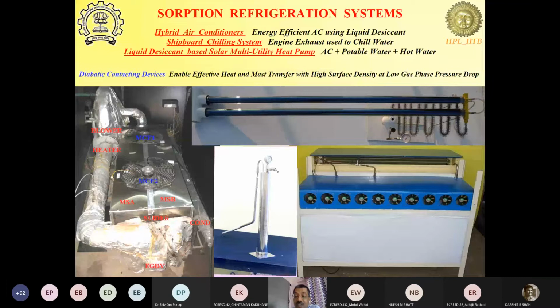And so the evaporator of conventional air conditioning systems, the conventional DX system, is typically operating at 7.2 degrees centigrade. While in the case of chillers, the chilled evaporator might operate anywhere between 3 to 5 degrees centigrade, depending upon the chilled water temperature and so on and so forth. But in this case, by using liquid desiccants to do the dehumidification, you will see that we can increase the evaporator temperature to 12 degrees, 15 degrees, 18 degrees, or even up to 20 degrees, depending upon the application.